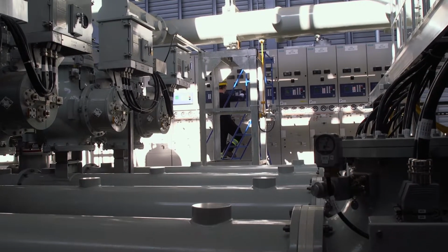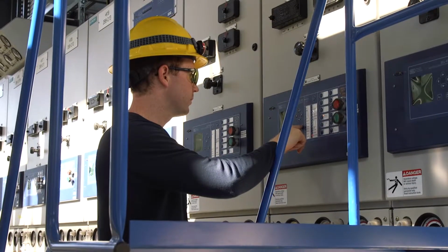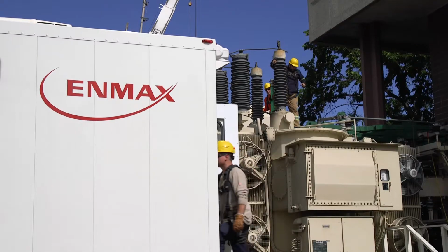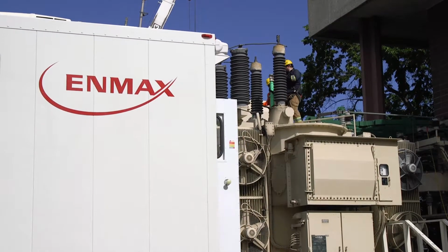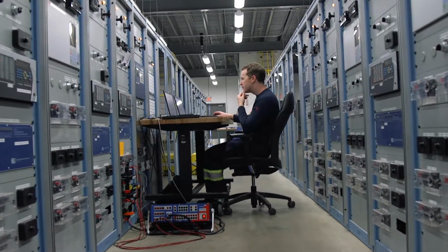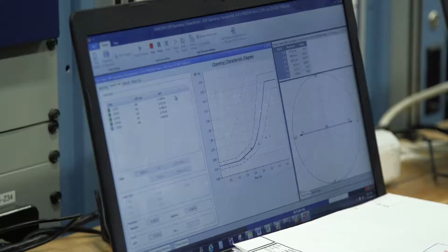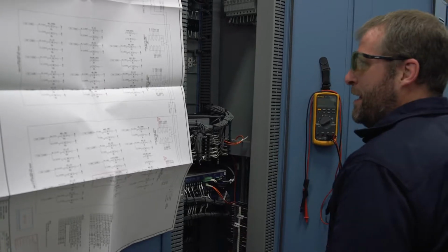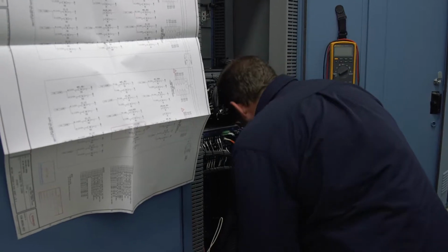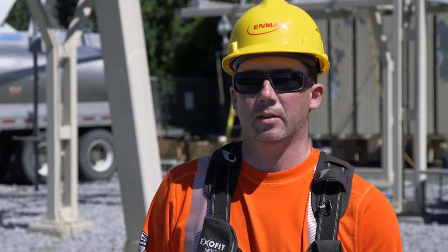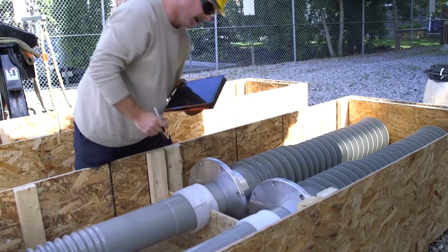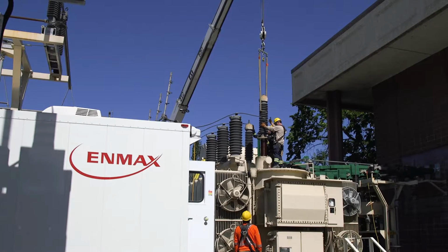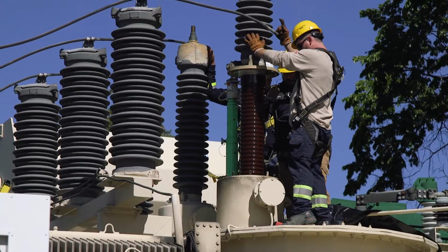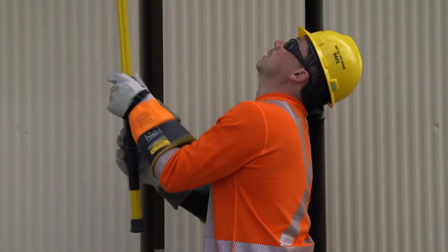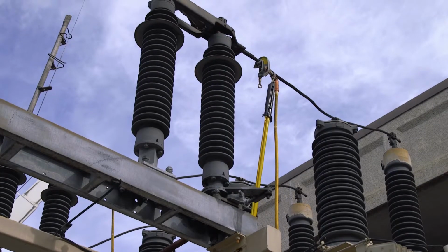Within the substation department, we have two different groups: protection and control, and apparatus repair and maintenance. The protection and control group install the relays, program them, test them, and do all the wiring and troubleshooting. The apparatus repair and maintenance group do routine maintenance, disassembling the equipment, putting it back together, and lubricating it. Anytime there's an outage, they go and repair the heavy equipment.